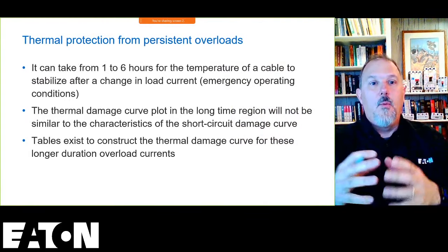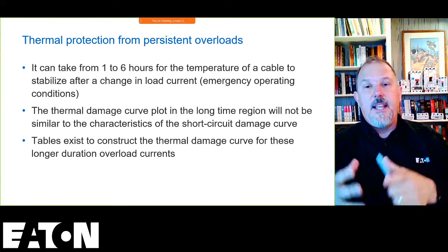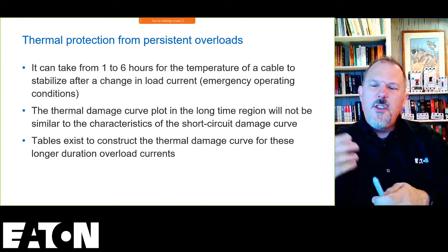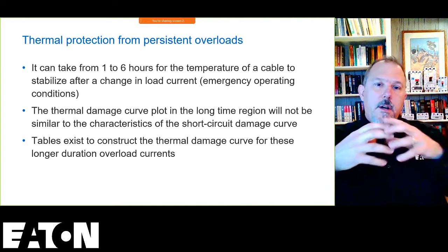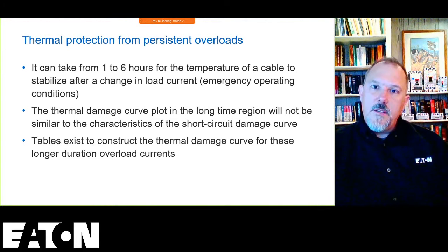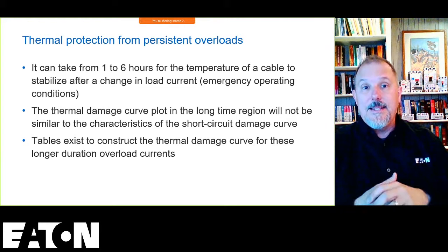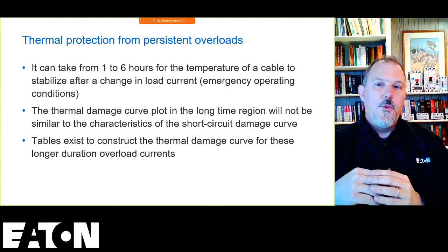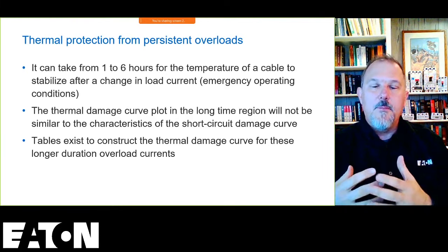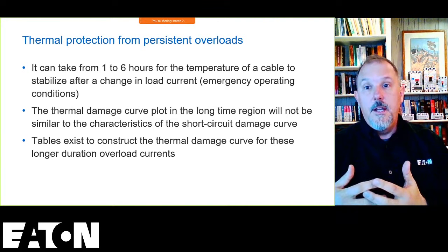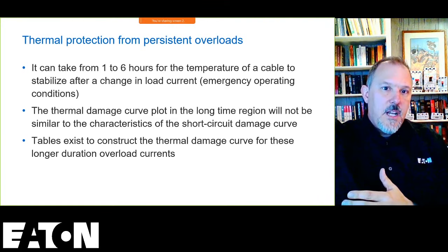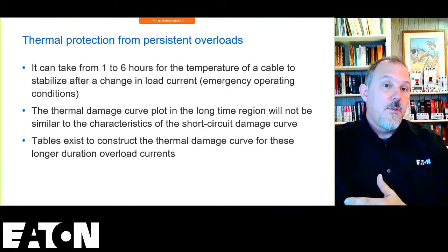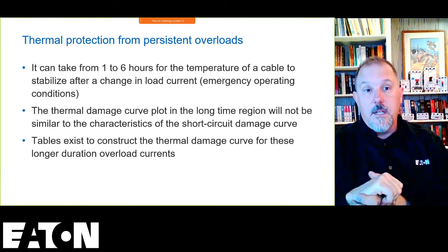Now, it can take about 1 to 6 hours for the temperature of a cable to stabilize after you change that load current. You have a conductor, a large mass of copper and insulation, that you need to raise the temperature of, and it takes about 1 to 6 hours to stabilize based upon changes in load current. So when you think about protection of a conductor due to overloads, you're talking a very long period of time of a persistent overload to start to impact damage to the insulation.